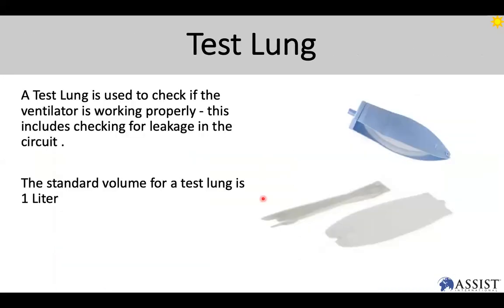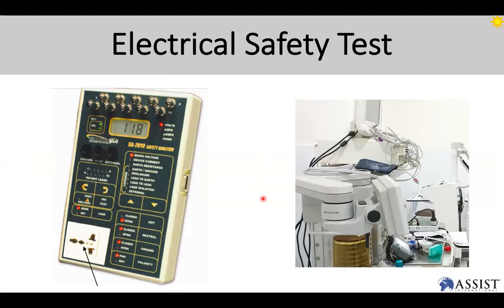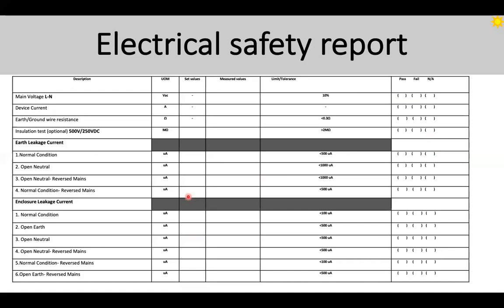I'm going to quickly go back and go through some electrical safety components as well. This is a very commonly found electrical safety analyzer. And here's a checklist of an electrical safety report. You're looking to verify the main voltage, the ground wire resistance, and you want to look for earth leakage current and the enclosure leakage current measurements. If you need this checklist, we're happy to share this with you.